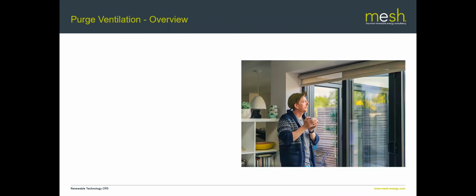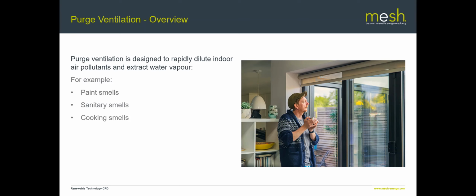And finally, we're going to look at this idea of purge ventilation. Purge ventilation is not something you're using every day, but it is needed, and typically it's there to get rid of things like smells. That could be sanitary smells, it could be painting, it could be cooking smells, and generally in most houses that is provided by openable windows. So you should not need to open your window (purge ventilation) in order to properly ventilate the house for day-to-day living. You should be able to live in the house quite happily with all the windows shut, and there should be good indoor air quality under most circumstances. And you then use purge ventilation when you have a particular need to provide very high levels of ventilation for short periods.